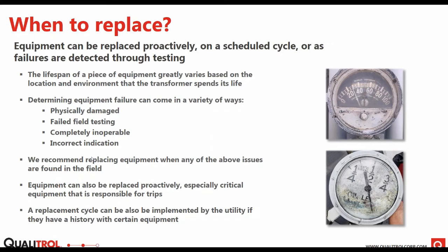And when it comes to critical equipment, such as a sudden pressure relay that trips your transformer, it's sometimes beneficial to replace those proactively. So, for example, you're on site with a scheduled 6-year maintenance program, and you notice that the sudden pressure relay is 40 years old, and it's still working, but it could be a good idea to replace it, because a failure of that magnitude could be much more expensive than the piece of equipment on the transformer.